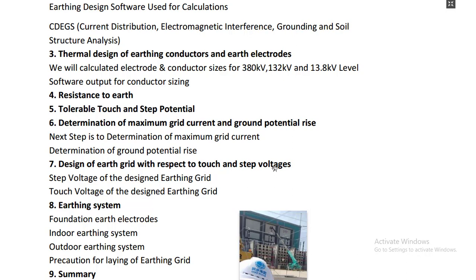These calculations are relatively straightforward. For earth resistance, we calculate it based on the data collected: the soil resistivity results taken at different points, which are entered into the software along with the fault level. We then calculate the step and touch potential to ensure they are within the limits of the provided specifications, and at the end we get an earth resistance value that will be within the required limits.